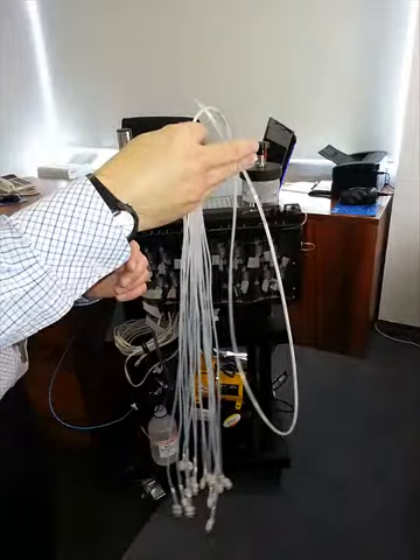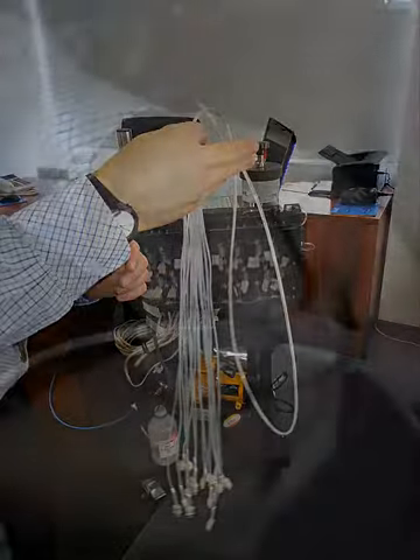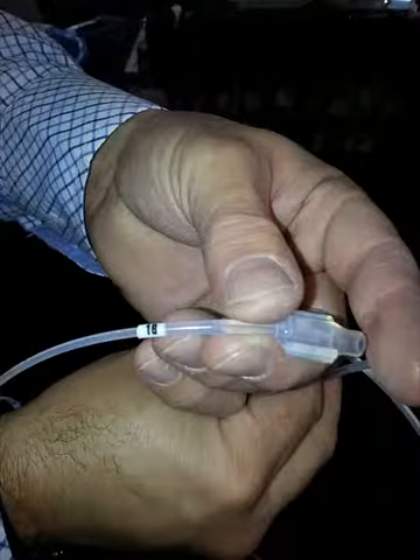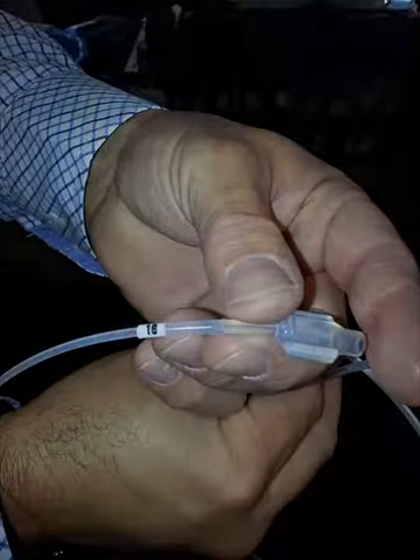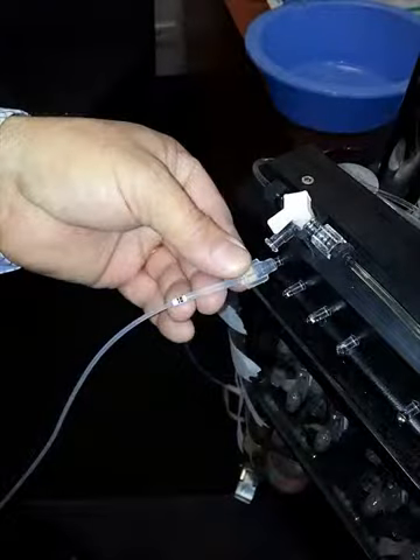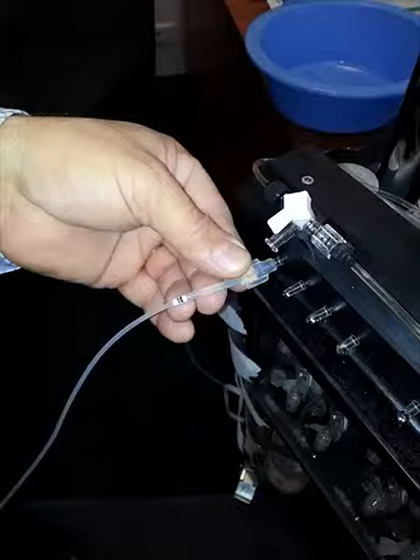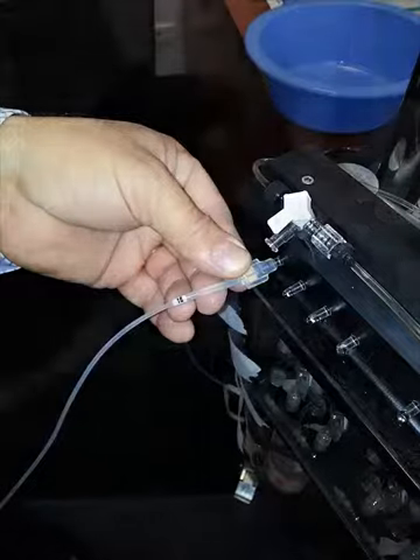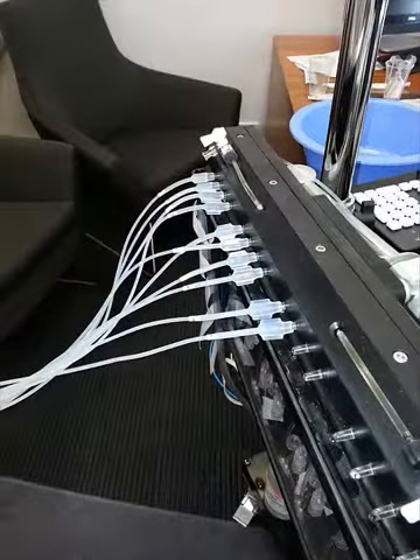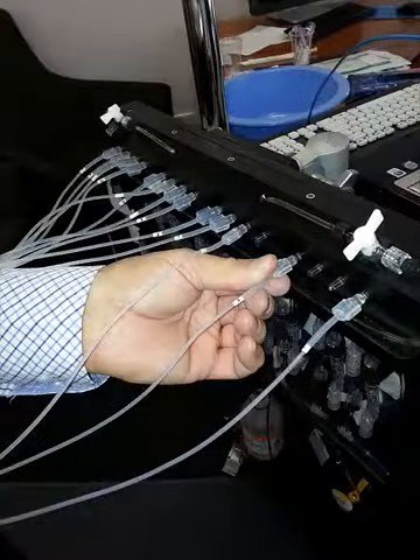Now it is time to attach the manometry catheter. Hold the catheter up by the hub and disentangle the connector tubing. Locate channel 16, which will be in the outer ring of tubes. Attach this to the left-hand end of the line of connectors. You will find that channel 15 is adjacent to channel 16 on the catheter if you rotate it clockwise, and so on down to channel 7. Channels 1 to 6 will need to be attached by locating the appropriate connector.